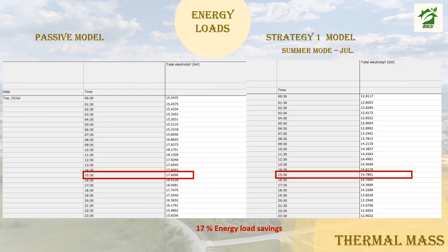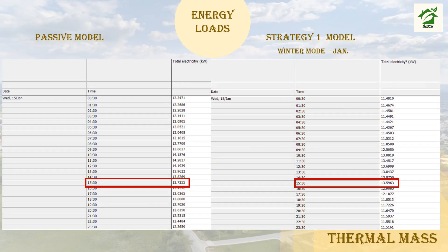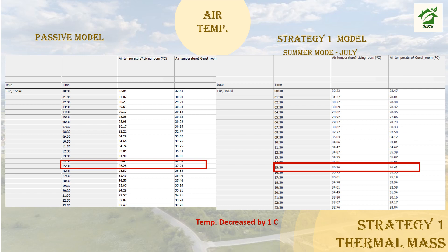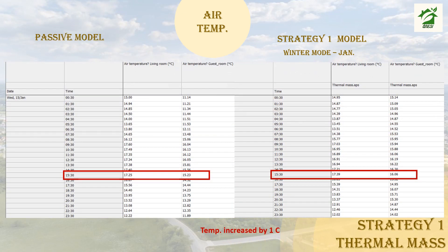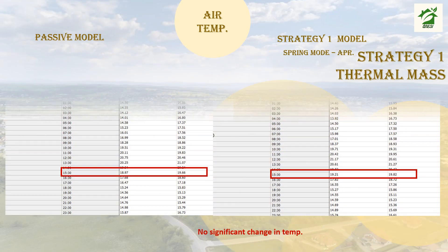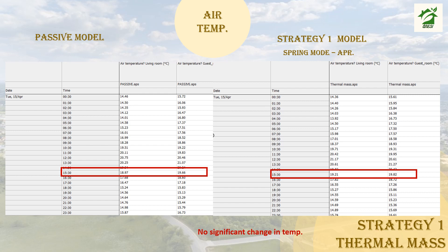After applying strategy one, the thermal mass model achieved additional energy load savings compared to the passive model. Additional savings were also noted in winter after applying the thermal wall and slab. A further reduction of 8% was noticed in spring. With the thermal mass strategy, the temperature in summer decreased by 1 degree Celsius, showing this strategy is effective in summer. In winter, the temperature increased by 1 degree Celsius, which is considered an enhancement. In spring, no significant change in temperature was noted after applying thermal mass.